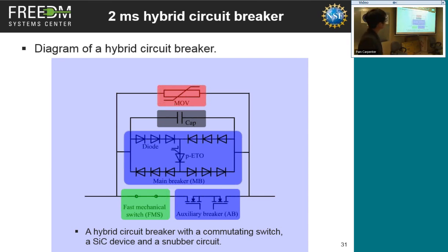We have that 1 millisecond mechanical switch, and then we want to build this hybrid circuit breaker. This is our topology - we have the fast mechanical switch here, an auxiliary breaker here, and we use the silicon carbide ETO in the bridge topology. We also put a capacitor here because we think it can greatly enhance the turn-off capability of the silicon carbide device, but it does not really affect its overall operation time.